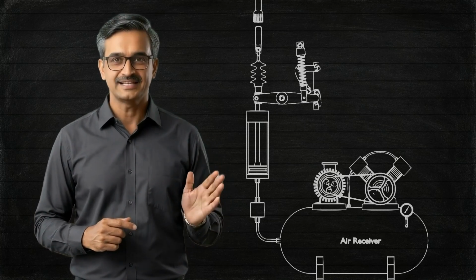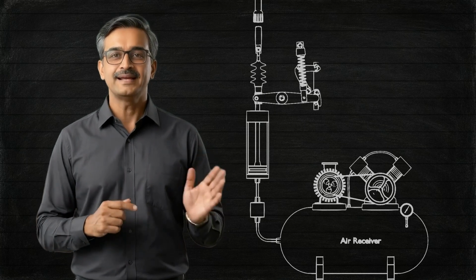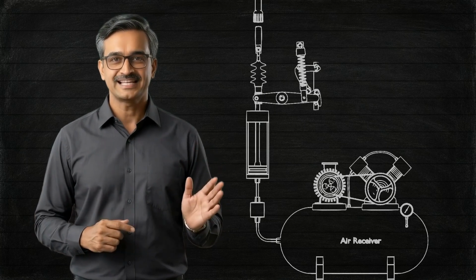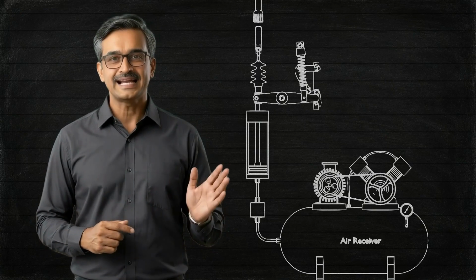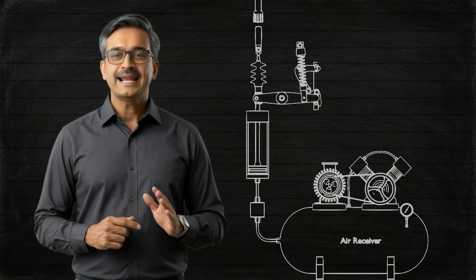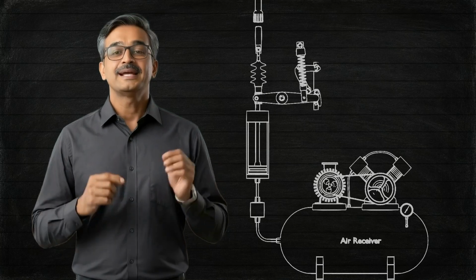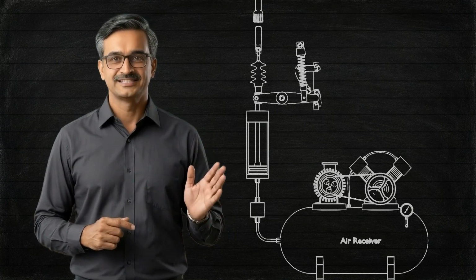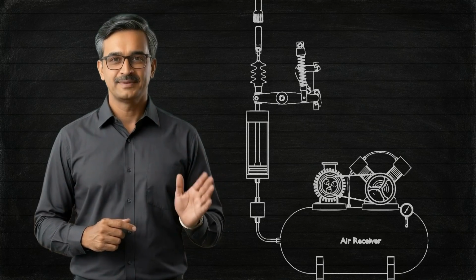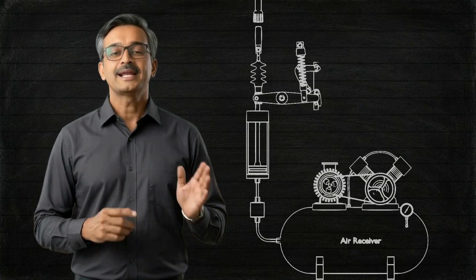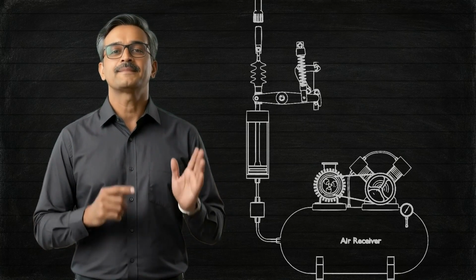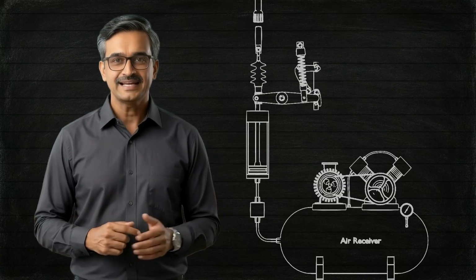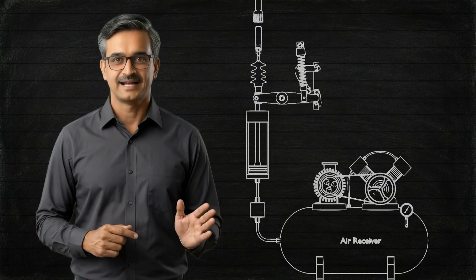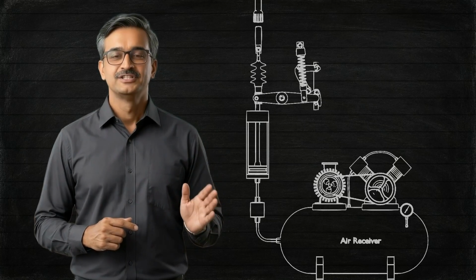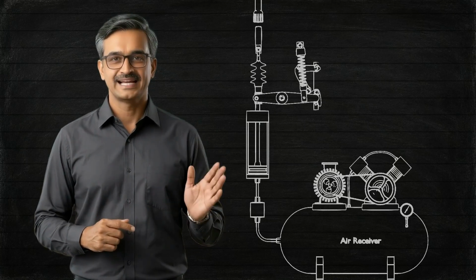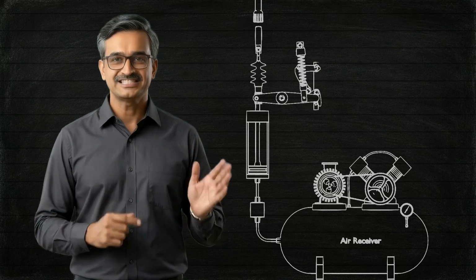Now imagine the breaker is standing in the open position. Nothing is moving. But inside the air receiver, compressed air is already stored. The air is already under pressure. That means the energy is stored in advance. Now suppose the operator presses the close push button locally or from the remote control panel. The very first device to operate is the solenoid-operated pneumatic valve. Normally it remains closed. But the moment the solenoid energizes, the valve opens instantly.